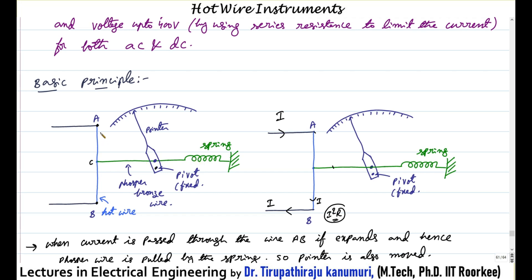Under normal conditions, the length AB is stiff. When the current I is passed through this wire, because of the current there will be I square R loss. Because of this, the temperature of the material increases, and when the temperature is increased, the wire will start expanding, getting a sag of S.